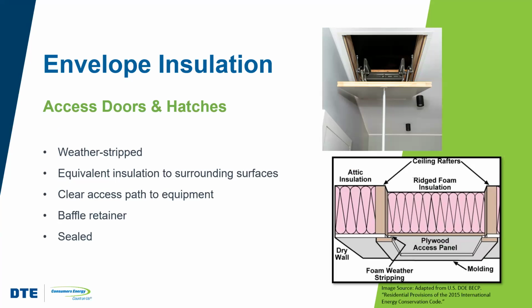Now, in a good design, attic doors and hatches will be weather stripped and insulated. The R value of the insulation will be the same as the R value of the surrounding surfaces. So, for example, if the ceiling is insulated to R38, then the access hatch will also be insulated to R38. If the ceiling is insulated to R49, the access hatch will also be insulated to R49. That hatch or door will also have a baffle to prevent the insulation from falling out when the hatch or door is opened. And if there's any equipment that may need servicing, there will be a clear path to it. And that path will be such that no insulation is damaged, stepped on, or compressed in our getting to that equipment.